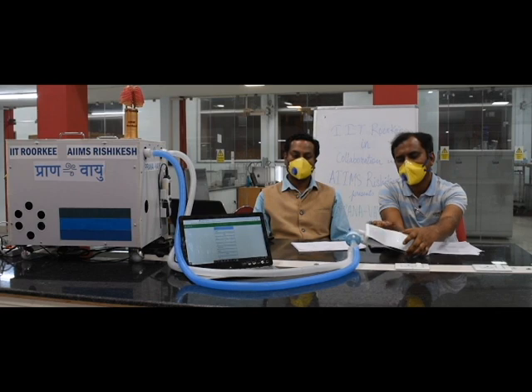Right. Now I'll be showing you that this is working in synchronized intermittent mandatory ventilation. That means it will go for a mandatory ventilation, and in between, if the patient wishes to take his own breath, then it will go for the pressure support mode. Here we have set the time window as 1 second. If the patient takes a breath within that time window, before the mandatory breath, it will support it as ACV mode. Okay, so let me show you how it is happening.